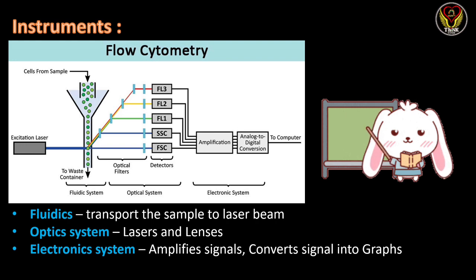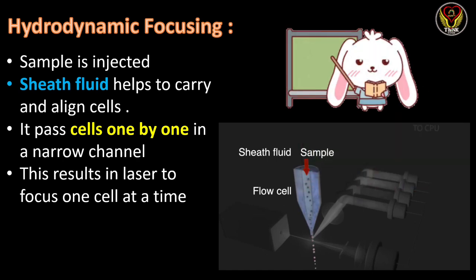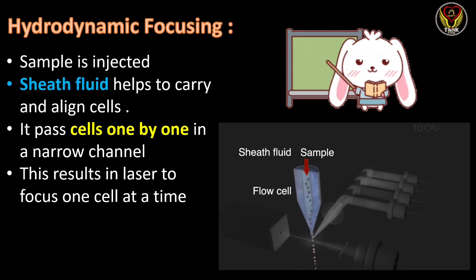The first principle is hydrodynamic focusing. Hydro means water or liquid, dynamic means moving, and focusing means concentrated. Simply, it is the focusing of the cells by moving them in a liquid medium. This helps the cells to move in a flow one by one. If the cells move without a flow, they will form clusters and some cells may be hidden from the lasers. So a liquid sheath is used which gives pressure and makes the cells move in a flow one by one, so the laser can focus on one cell at a time.